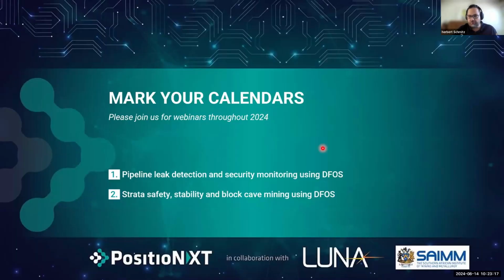This is my presentation for today on a nervous system for your underground mine. Keep in mind that ultimately fiber optics allows us to continually measure the temperature throughout the entire mine. And we can use that data for fire detection, for heat stress monitoring, for ventilation efficiency, and integrate that with current third-party systems, SCADA and control, and ultimately assist with this whole drive in mining to get to ventilation on demand. We have some upcoming webinars for pipeline leak detection and security monitoring, as well as strata and rock stability and block caving using fiber optic sensing. So have a look out on LinkedIn and the SAIMM calendar, and please mark this.